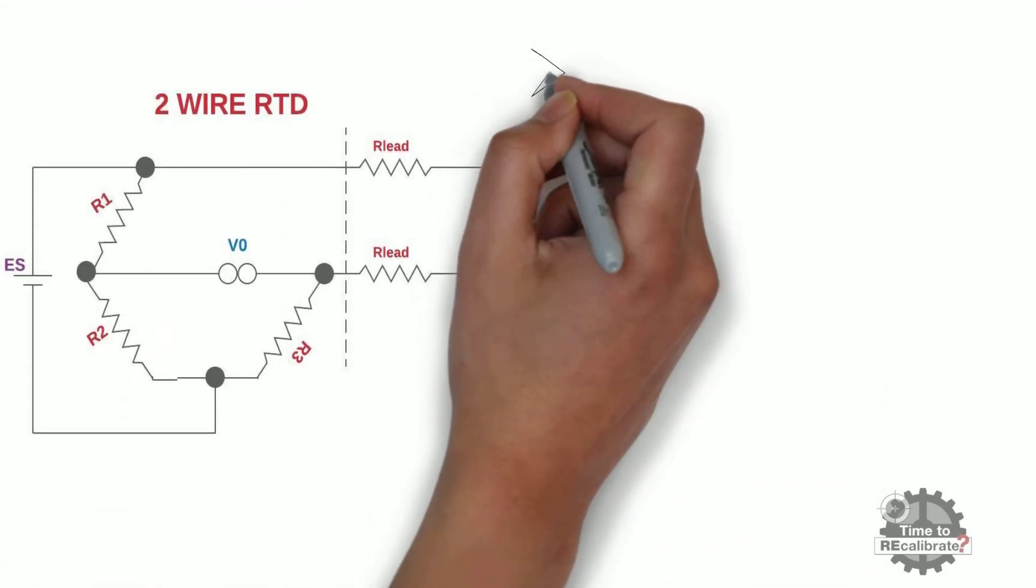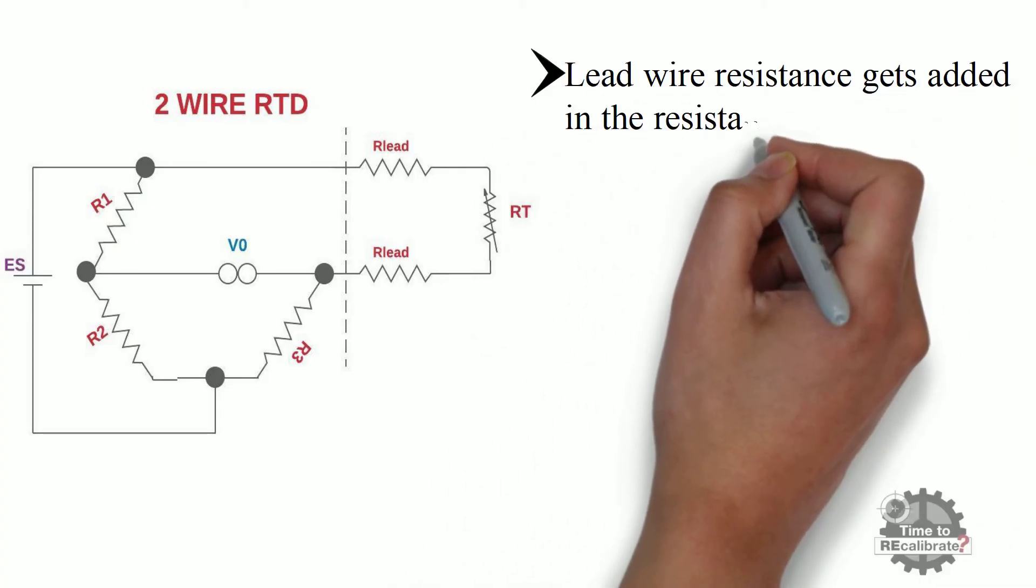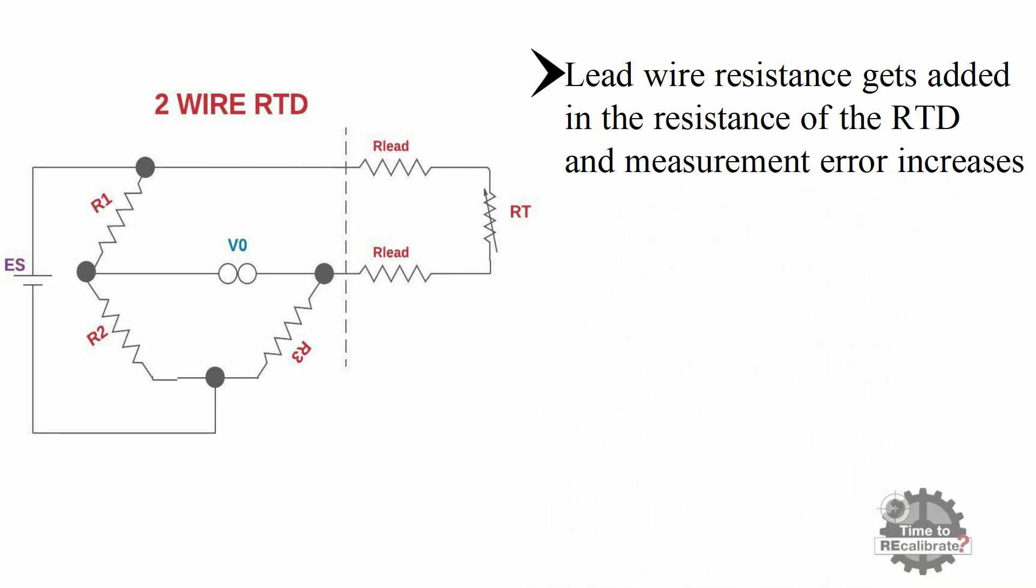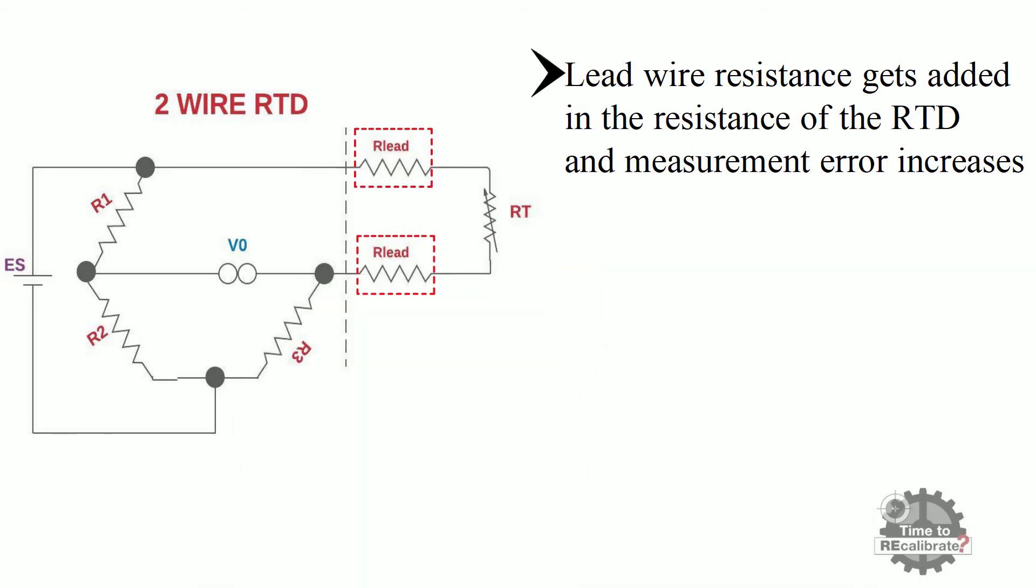As you can see from the circuit diagram of 2-wire RTD, lead wire resistance gets added to the resistance of the RTD, and because of lead wire, the measurement error also increases. The measurement error increases with increase of distance between the temperature transmitter and the RTD position. In this circuit diagram, R1, R2, and R3 are Wheatstone bridge resistors. R lead is the resistance of those particular lead wires, and RT is the resistance of the RTD.